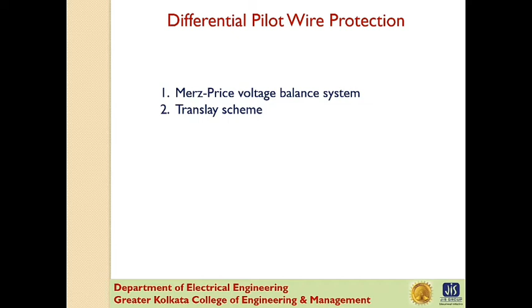Now this figure shows the single line diagram of Merz-Price voltage balance system for the protection of a three-phase line. Identical current transformers are placed in each side at both ends. The pair of CTs in each line is connected in series with a relay in such a way that under normal condition their secondary voltages are equal and in opposition, that is, they balance each other.